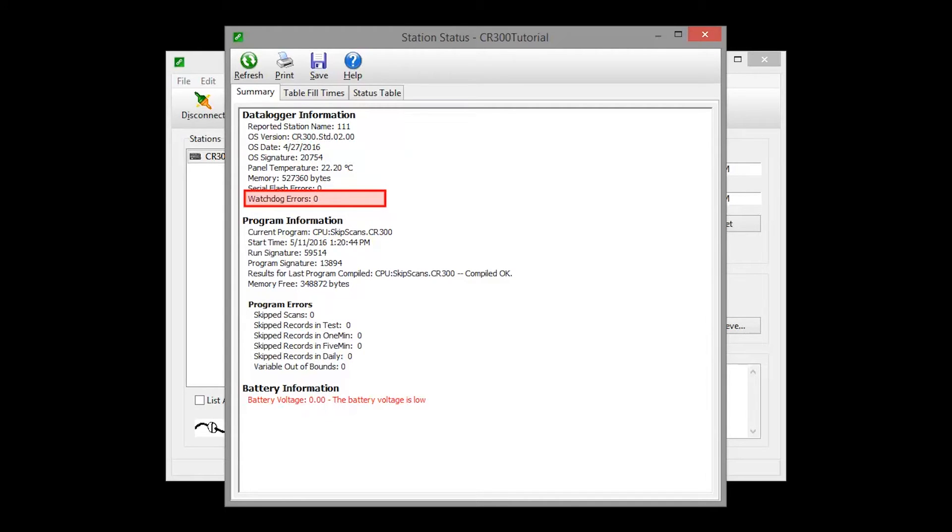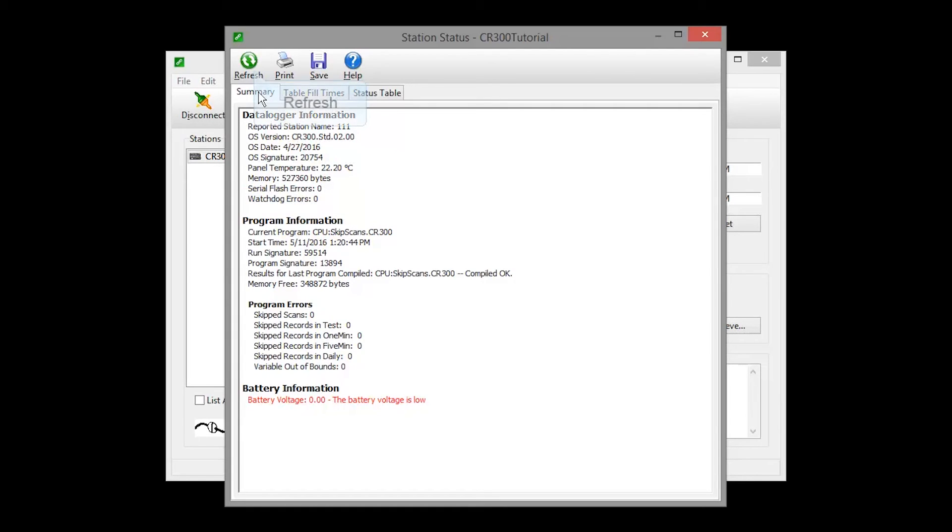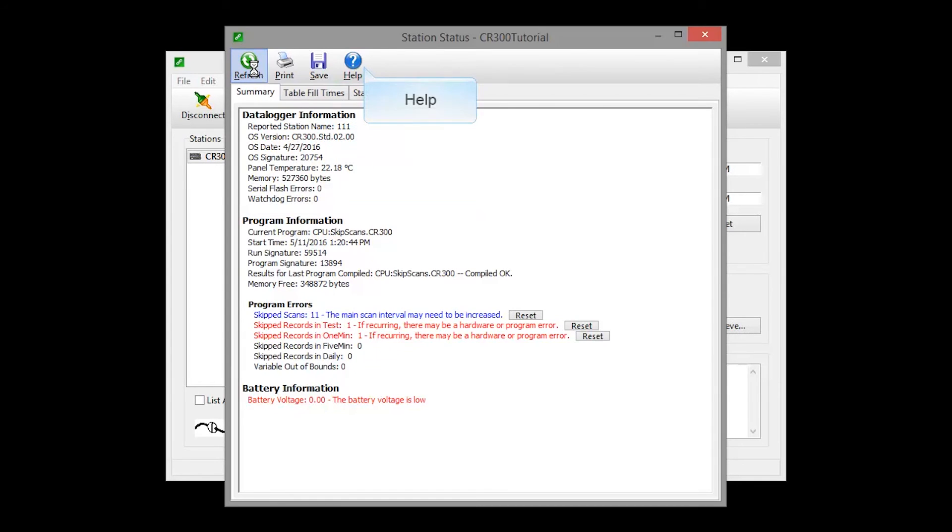If the watchdog counter continues to accumulate, the data logger probably needs an operating system update or a hardware repair by Campbell Scientific. The refresh button causes LoggerNet to query the data logger and update the status table values again. For more information, read the help topics.